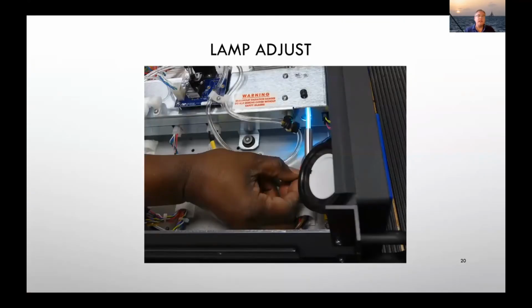The technician here is exposing the UV lamp. A couple of things here. Generally speaking, you don't need to pull the lamp all the way out like this unless you're swapping it out, and these do tend to occasionally get unstable and do need to be replaced.